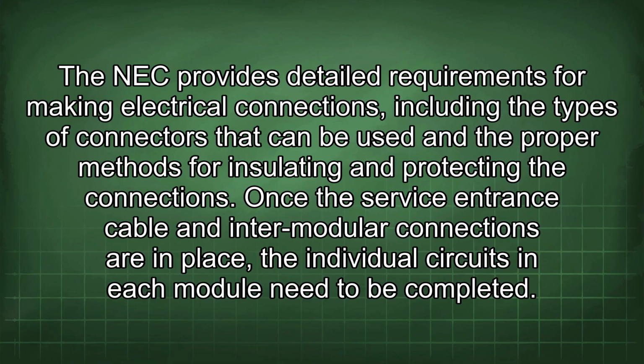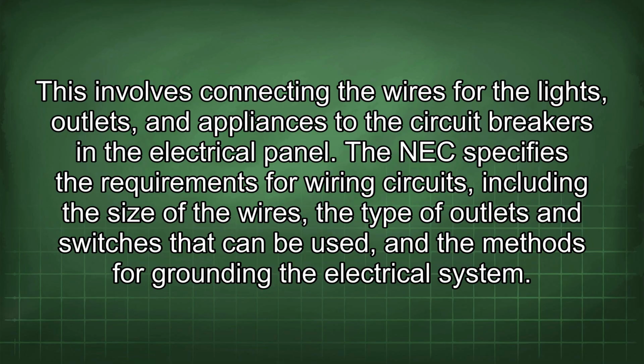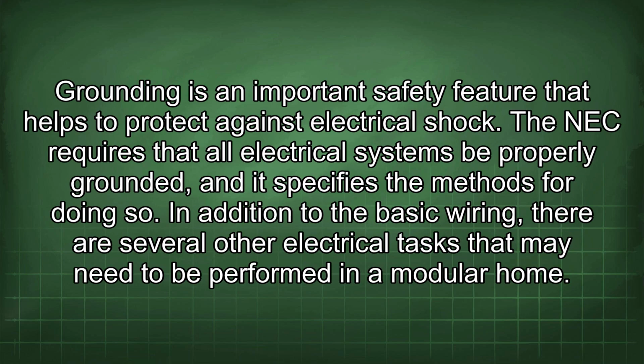Once the service entrance cable and intermodular connections are in place, the individual circuits in each module need to be completed. This involves connecting the wires for the lights, outlets, and appliances to the circuit breakers in the electrical panel. The NEC specifies the requirements for wiring circuits, including the size of the wires, the type of outlets and switches that can be used, and the methods for grounding the electrical system. Grounding is an important safety feature that helps protect against electrical shock, and the NEC requires that all electrical systems be properly grounded, specifying the methods for doing so.